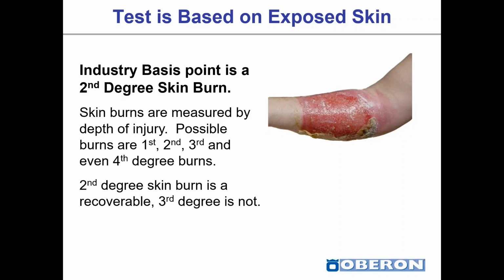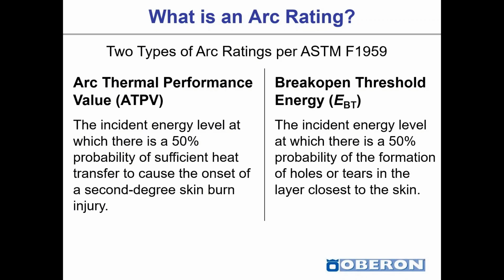So we want to avoid that third-degree skin burn injury at all costs possible. What is an arc rating? There are two different types of arc ratings defined by the ASTM F1959 standard. We have the ATPV, or arc thermal performance value, which is the incident energy level at which there's a 50% probability of sufficient heat transfer to cause the onset of a second-degree skin burn injury. And then we have the break open threshold, or EBT, at which the incident energy level is a 50% probability of the formation of holes or tears in the layer closest to the skin.